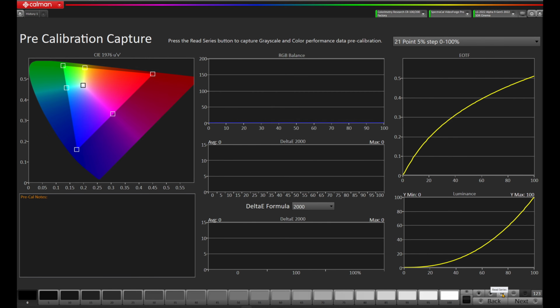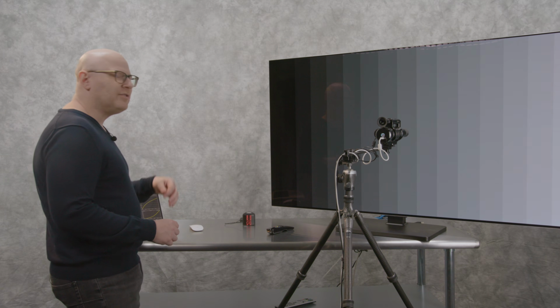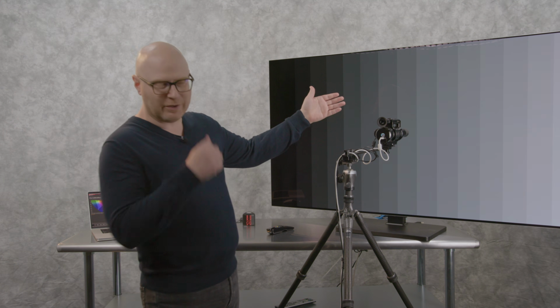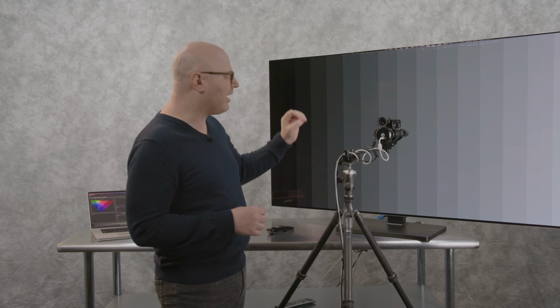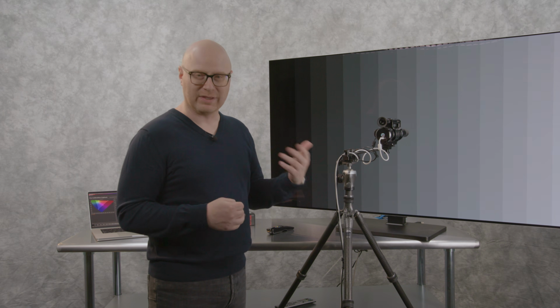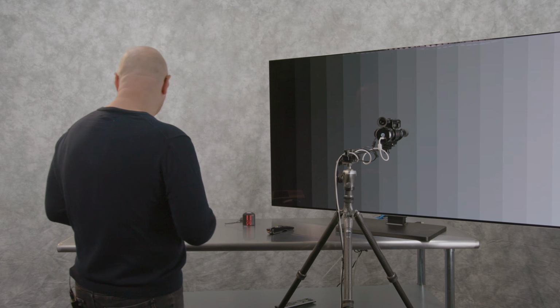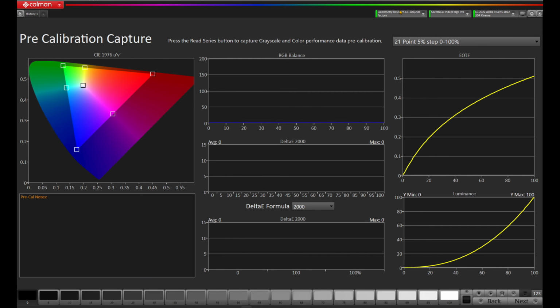Here, we're going to take a pre-calibration capture, but you'll notice I'm using the CR100 and the CR300. What I haven't done yet is optimize my meters for use with the calibration. I'm actually going to take a step here, go up to the meter panel, and start setting up my meter.